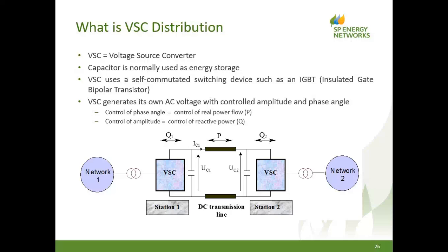If we can control the AC voltage correctly, we can control both the amplitude and the phase angle of the voltage. So effectively, we become a de facto generator, albeit with no rotational inertia. But if we do this properly and control the phase angle of the voltage that we generate with respect to either network 1 or network 2, we can control the flow of real power between the two networks. If we can control the amplitude of the generated voltage on both network 1 and network 2 independently, we can control the flow of reactive power between the DC system and the AC system.